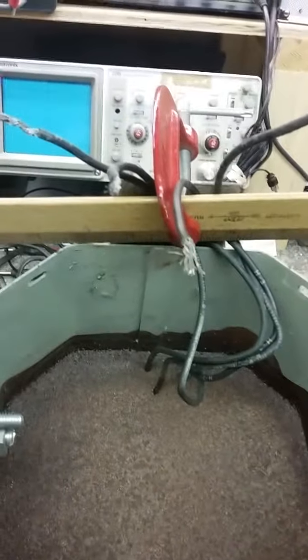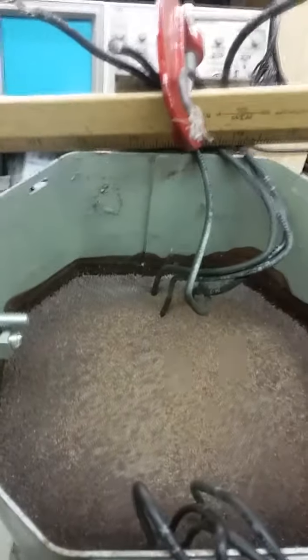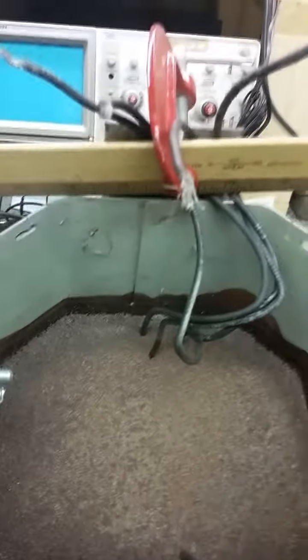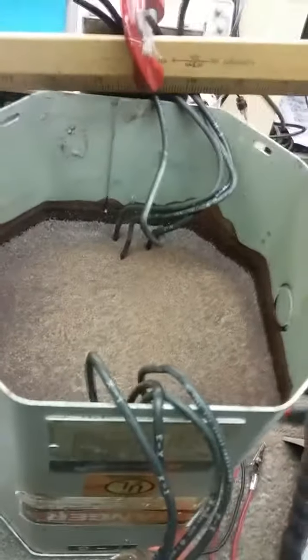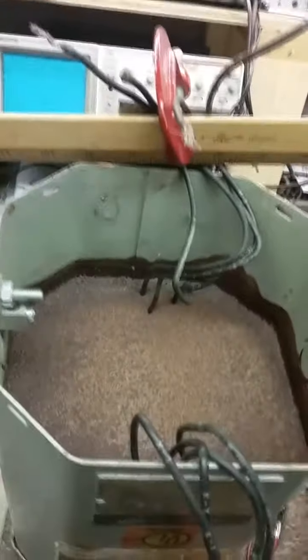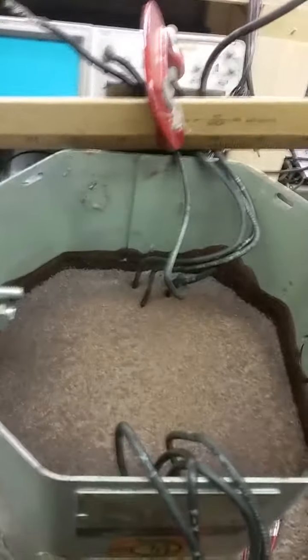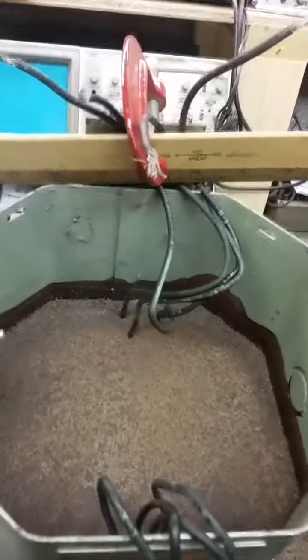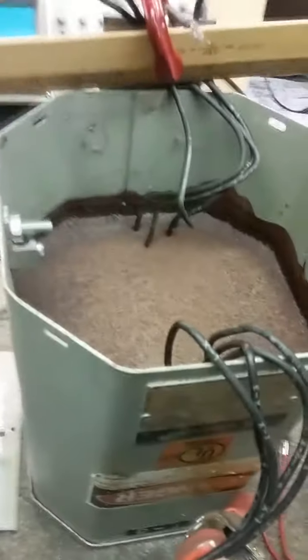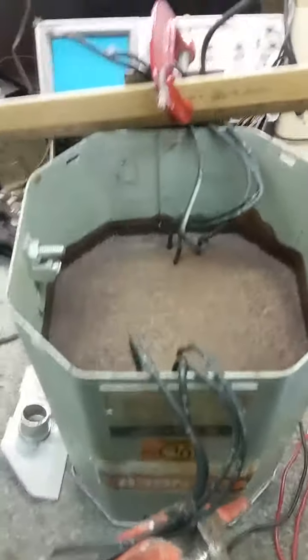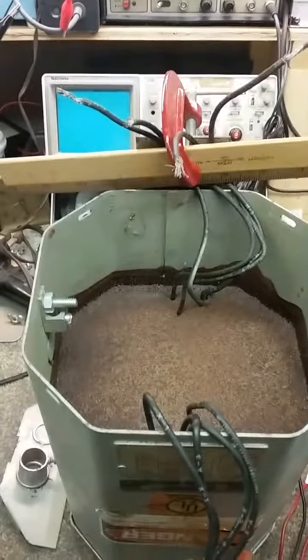If I did, at 120 volts, it's going to draw around 25 to 26 amps, because it's a 3 kilovolt-amp transformer. It would trip my breaker, basically, because that's more current than my breaker box will provide to this transformer. So I can't throw 120 volts input.